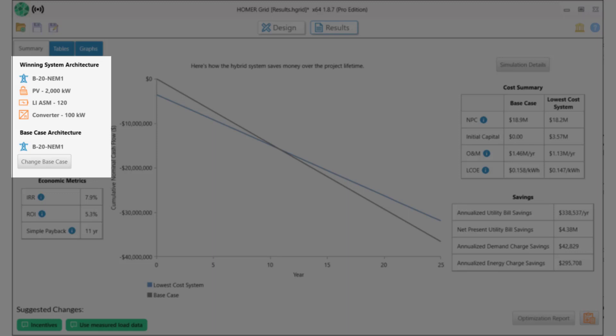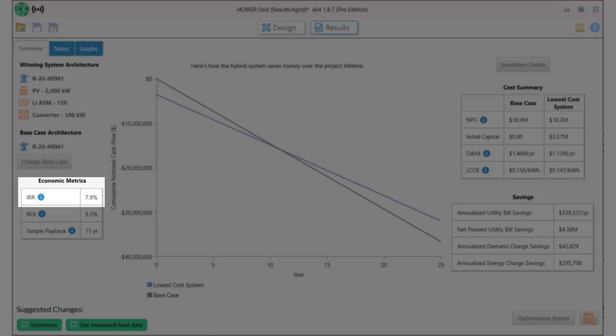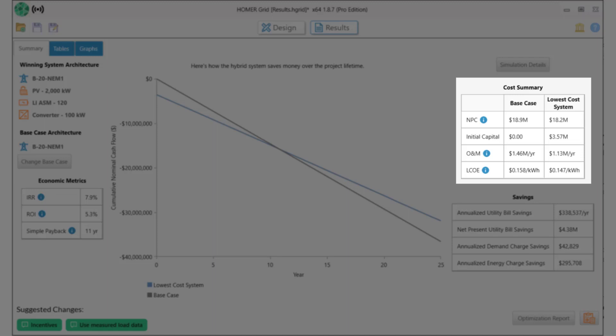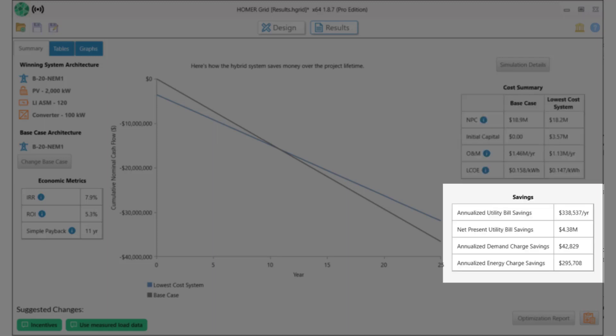The base case, which is the utility tariff we selected, is shown underneath that. This project has an internal rate of return of 7.9%, a 5.3% return on investment, and a simple payback of 11 years. To the right of the graph is a summary of costs for the two systems. The table below that summarizes the savings: $4.38 million.